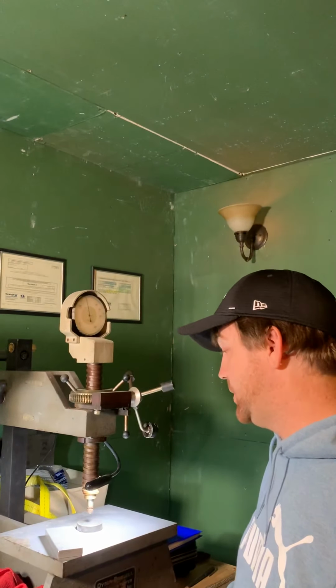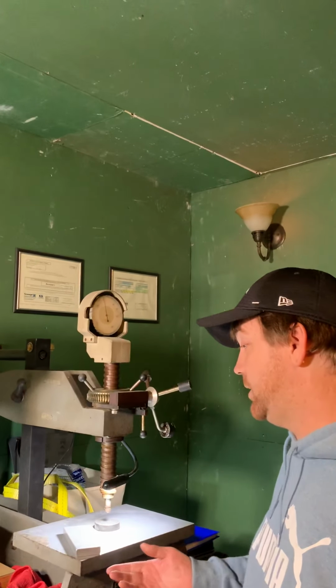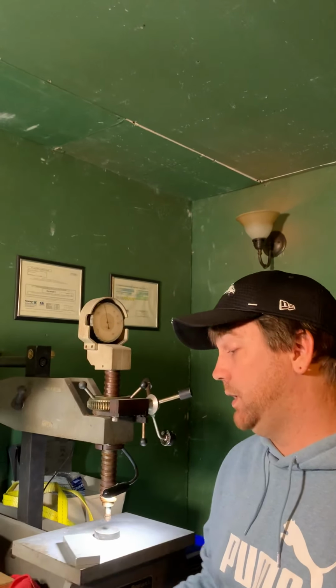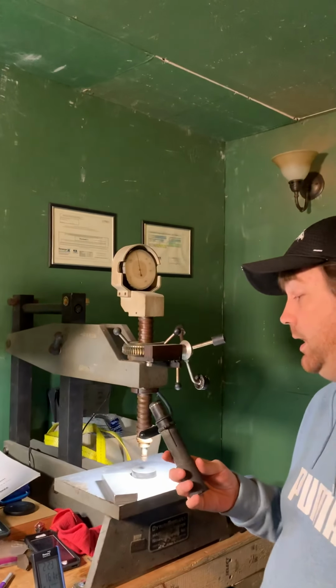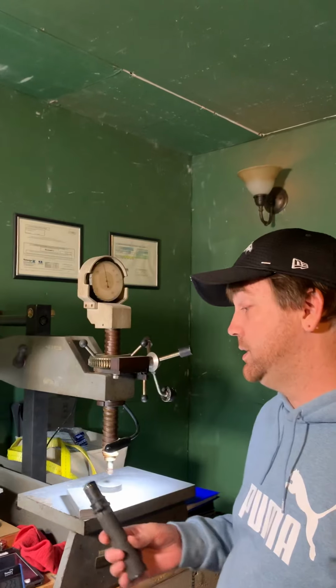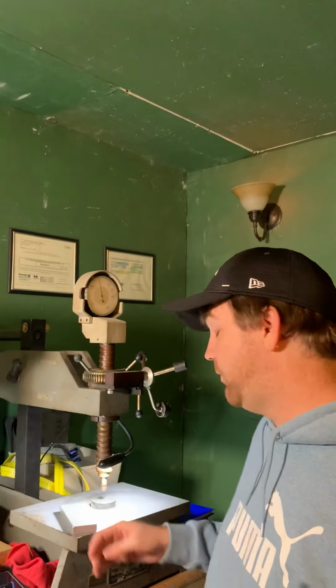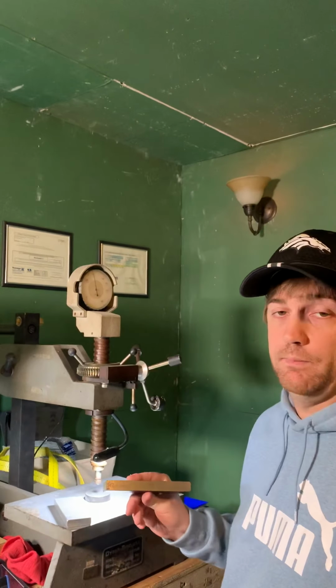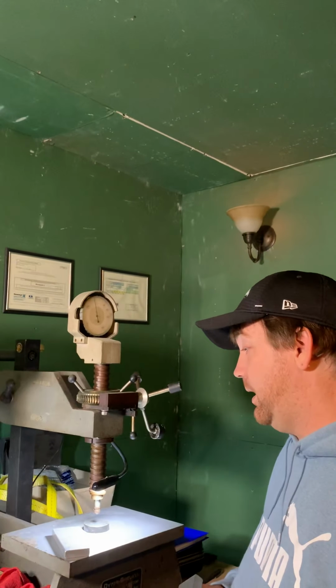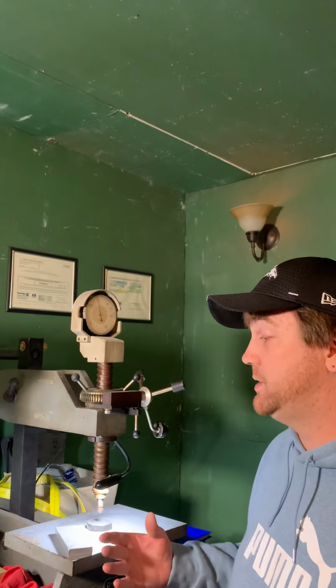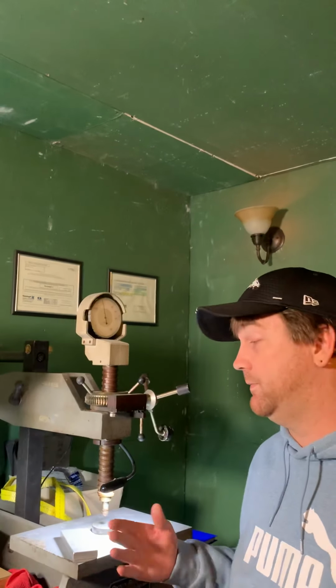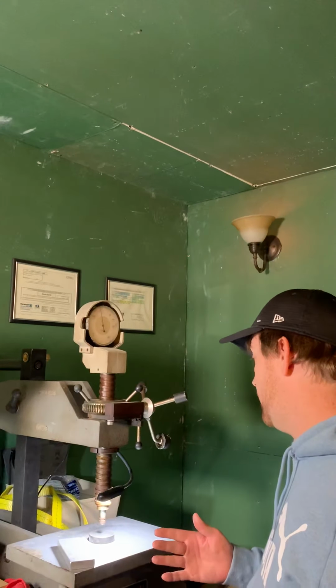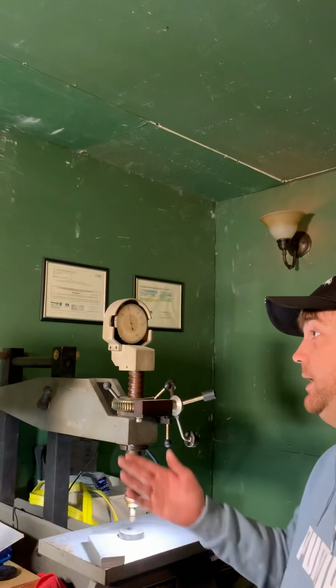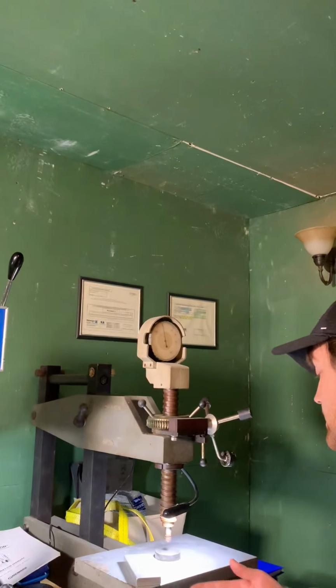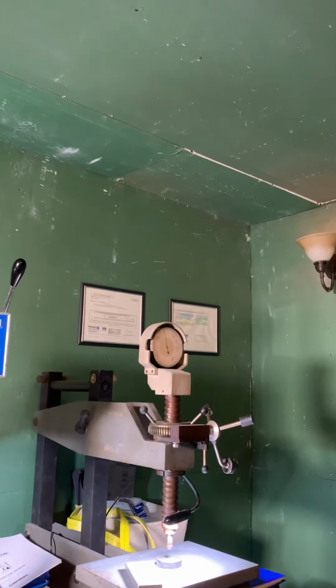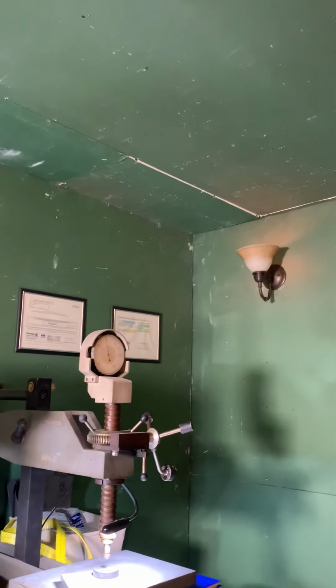For Brinell testing in particular, just ensure that the scope that you are using, the eyepiece, is clean, and that you compare it to a stage micrometer before taking a measurement on a test block. If it's not compared to a stage micrometer prior, you could be giving a false reading. But other than that, you adhere a sticker the same as the Rockwell tester, and that sums up the calibration and indirect verification for a Brinell tester.